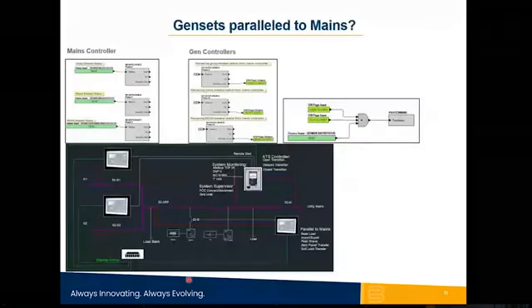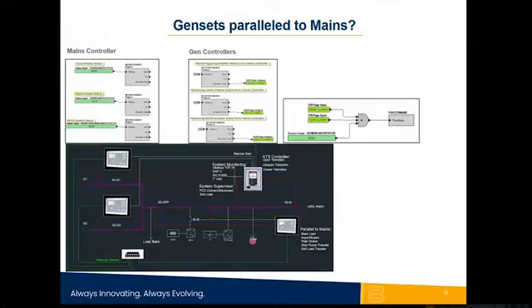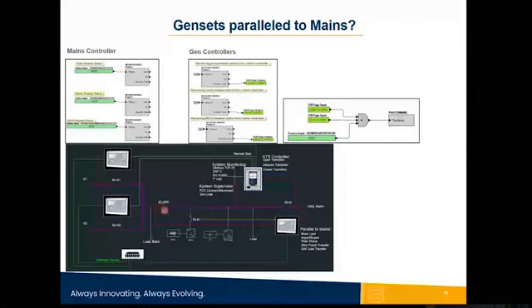In this system, the gens can be parallel to the grid or they can be parallel to the batteries. But how do we know what they're parallel to? We can implement distributed broadcast logic to determine that. So here, the mains controller is sending out the status of the group breaker, which is this breaker. So you can see this blue line right here. It's receiving breaker status and controlling that breaker.